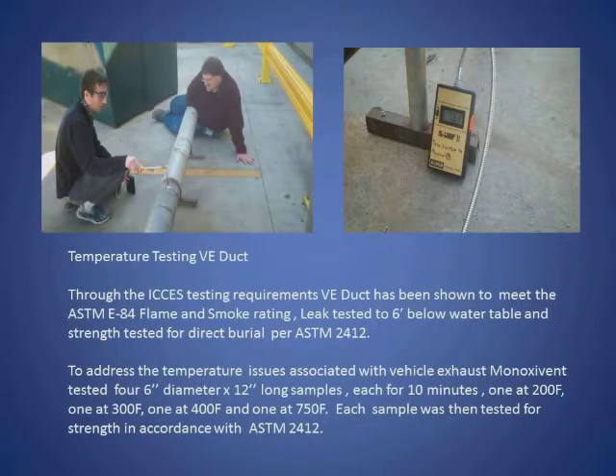Okay, the ICC testing didn't include anything for high temperature for vehicle exhaust. So what we did was we set up a procedure, and you see in the upper left photo, Sam and Brian, and we have two sheet metal duct sections that are 5 foot long, and we put a 1 foot long piece of the PE duct in the middle. And then we have a temperature probe to check the temperature, and the readout device is shown on the right. So we had a very good setup, and we maintained the temperature for 10 minutes.